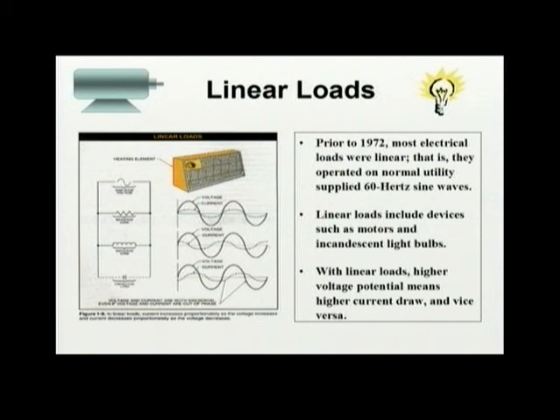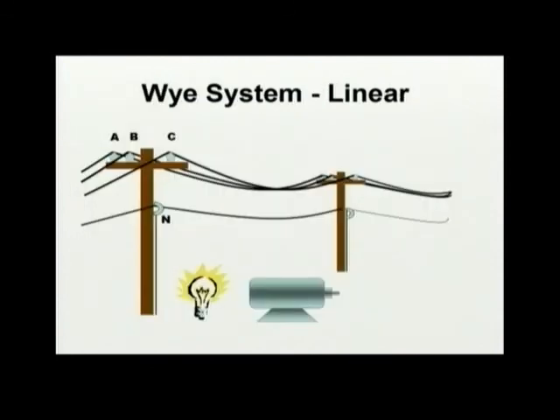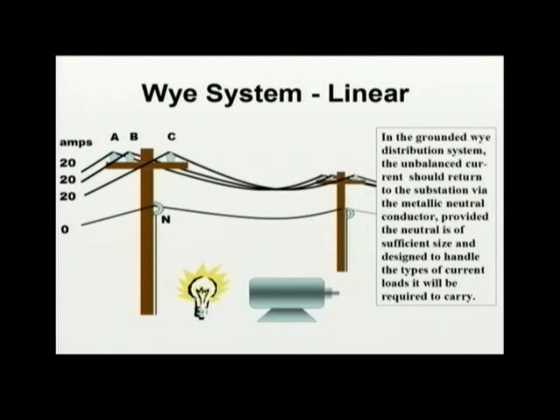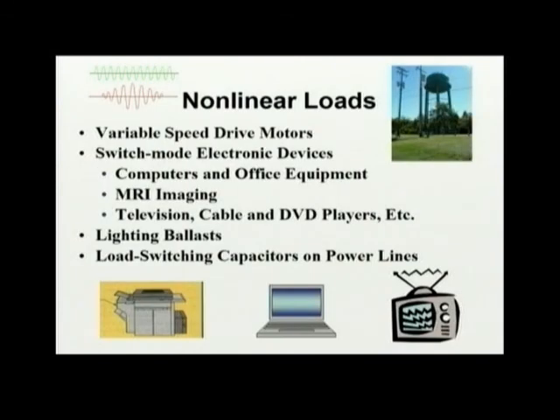Prior to 1972, most electrical loads were linear. That is, they operated on normal, utility-supplied 60 hertz sine waves, alternating current. In the grounded Y distribution system used throughout North America, the unbalanced current should return to the substation via the metallic neutral conductor, the lowest line in the photo, provided the neutral is of sufficient size and designed to handle the types of current loads it will be required to carry.